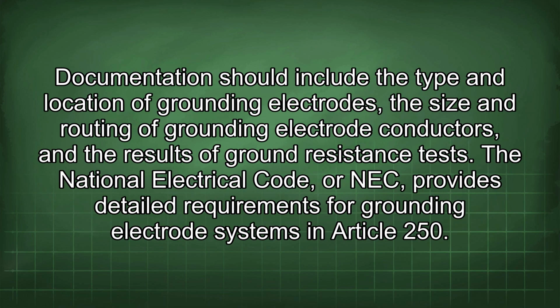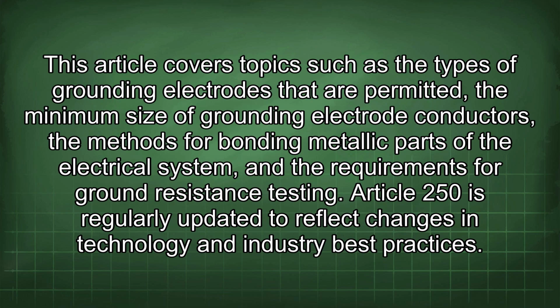Documentation should include the type and location of grounding electrodes, the size and routing of grounding electrode conductors, and the results of ground resistance tests. The National Electrical Code, or NEC, provides detailed requirements for grounding electrode systems in Article 250. This article covers topics such as the types of grounding electrodes that are permitted, the minimum size of grounding electrode conductors, the methods for bonding metallic parts of the electrical system, and the requirements for ground resistance testing.